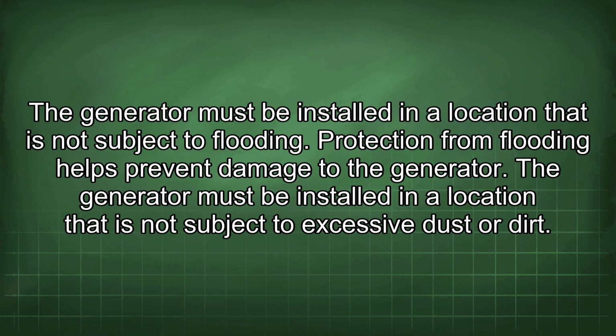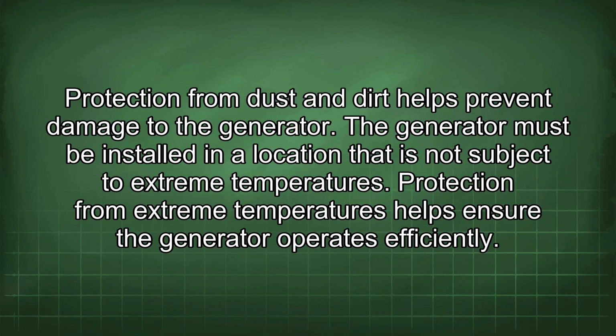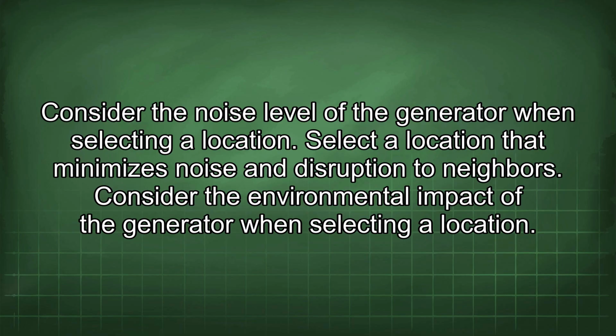The generator must be installed in a location that is not subject to excessive dust or dirt. Protection from dust and dirt helps prevent damage to the generator. A generator must be installed in a location that is not subject to extreme temperatures. Protection from extreme temperatures helps ensure the generator operates efficiently. Consider the noise level of the generator when selecting a location. Select a location that minimizes noise and disruption to neighbors.